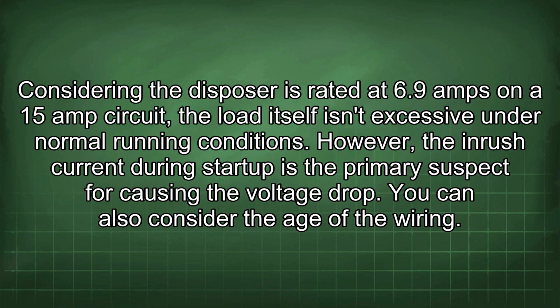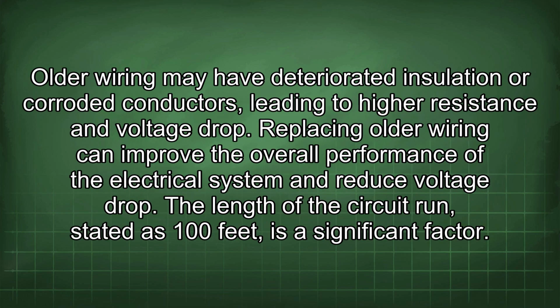Considering the disposer is rated at 6.9 amps on a 15 amp circuit, the load itself isn't excessive under normal running conditions. However, the inrush current during startup is the primary suspect for causing the voltage drop. You can also consider the age of the wiring. Older wiring may have deteriorated insulation or corroded conductors, leading to higher resistance and voltage drop. Replacing older wiring can improve the overall performance of the electrical system and reduce voltage drop.